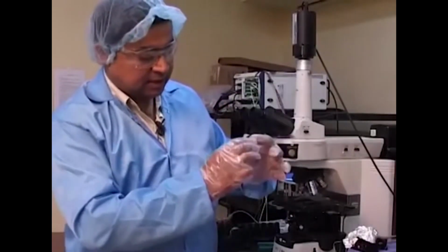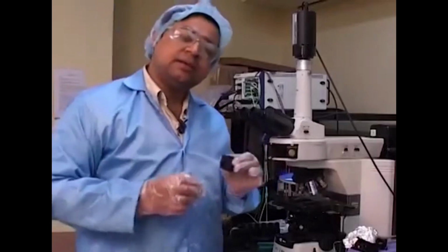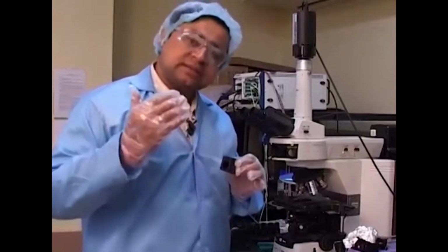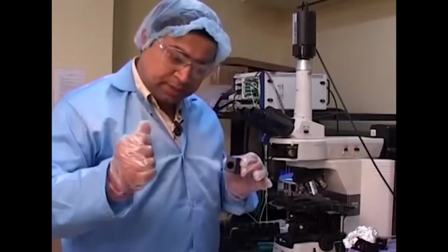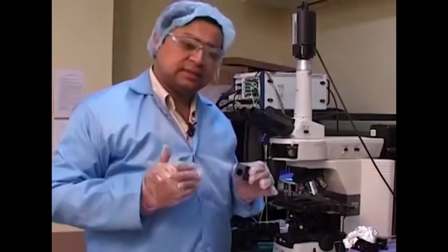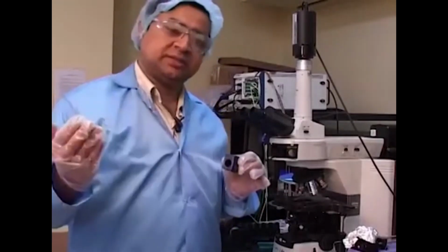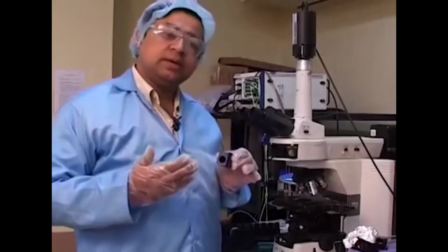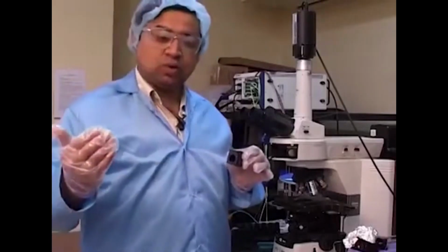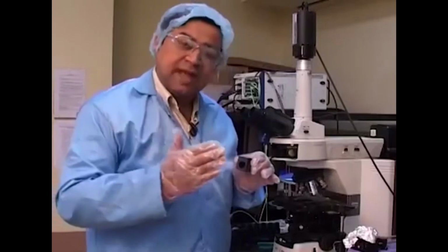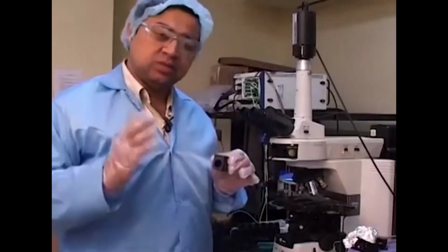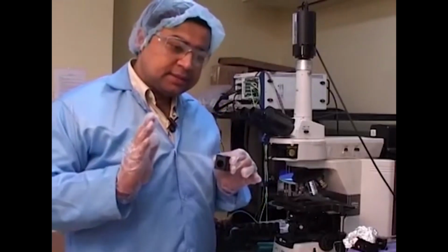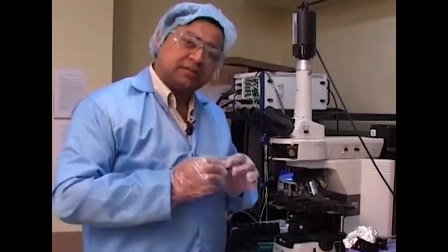There is also the dichroic mirror, which is placed inside this filter cube. Probably it is not visible from outside, but the way that mirror operates is also based on this cutoff principle. So there may be a cutoff wavelength beyond which the dichroic mirror may be able to refract the light, and below which it should be able to reflect the light. So that's how these mirrors are typically designed. Okay. Now with this combination in mind, let us look at what is the optics.